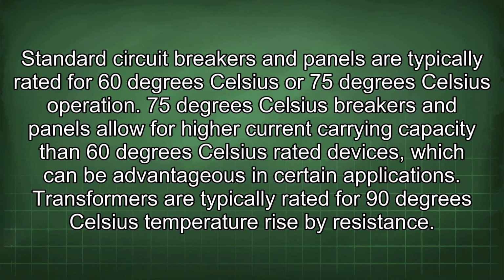Standard circuit breakers and panels are typically rated for 60 degrees Celsius or 75 degrees Celsius operation. 75 degrees Celsius breakers and panels allow for higher current carrying capacity than 60 degrees Celsius rated devices, which can be advantageous in certain applications.